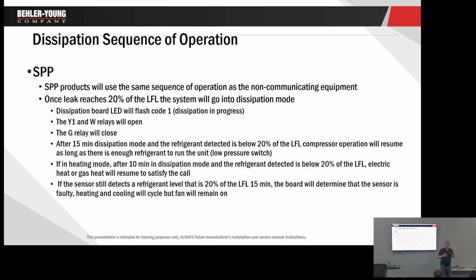So the idea there is the end user tells you, hey, the blower hasn't shut off on this thing in 3 days. Okay, then you know there's a problem. But the good news is the longest it can stay in mitigation is 15 minutes. So this morning, it would have been no heat for 15 minutes, and then it would have gone back into operation. The only difference was the blower would run all the time. Okay.